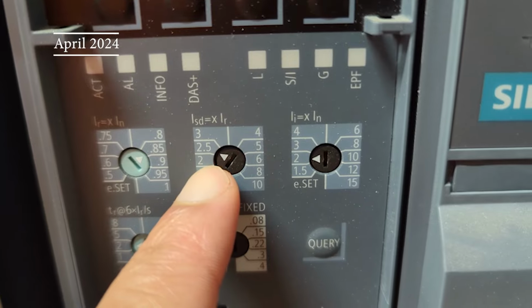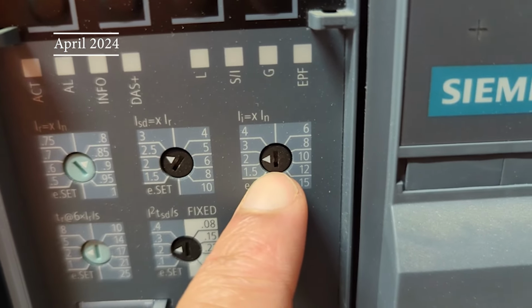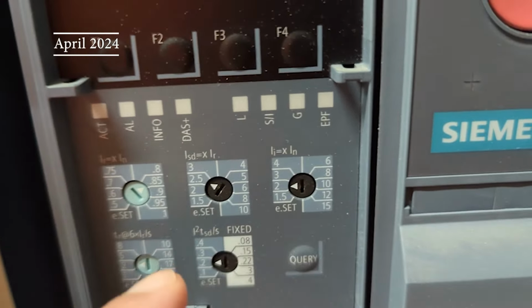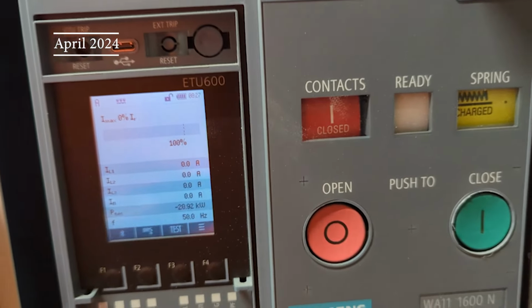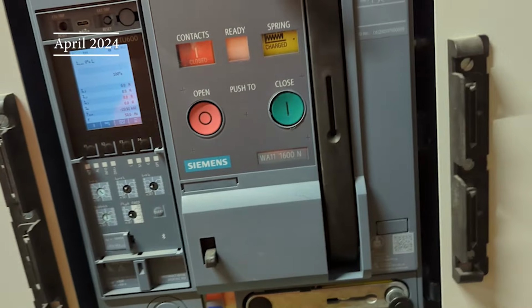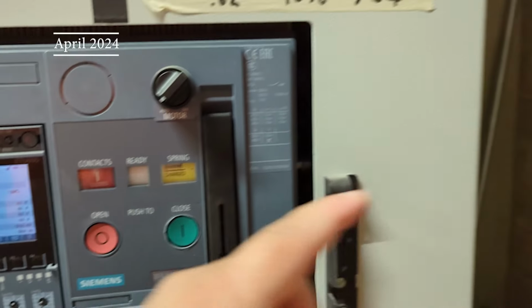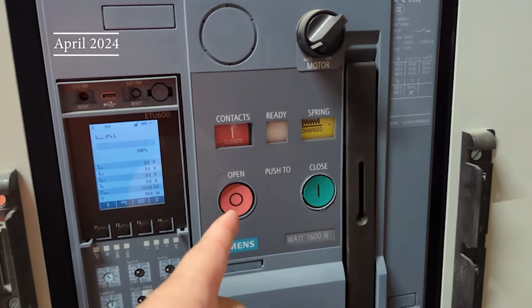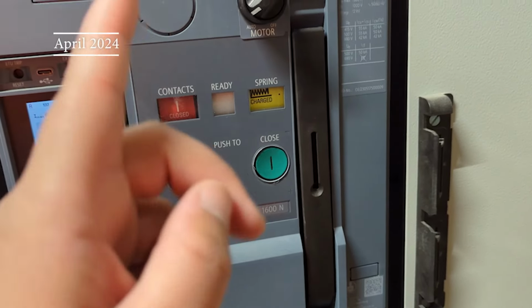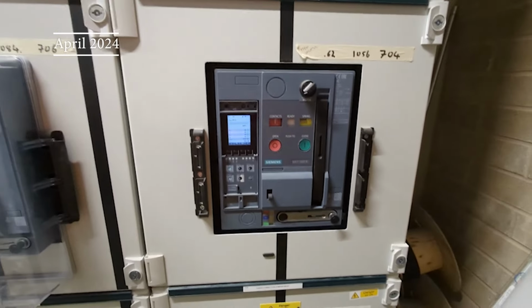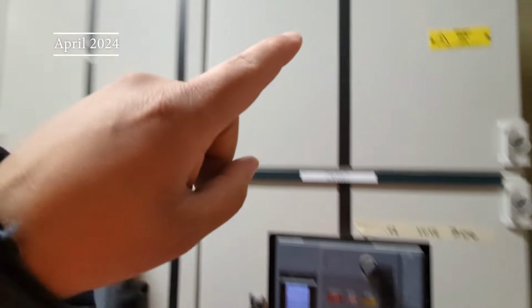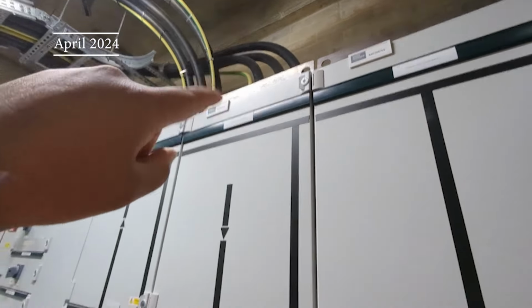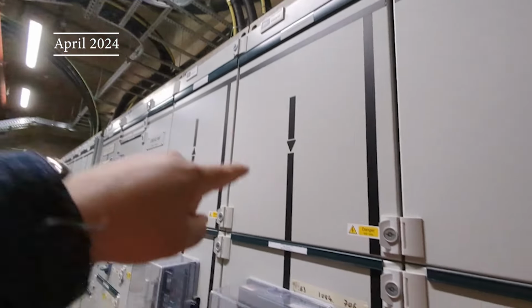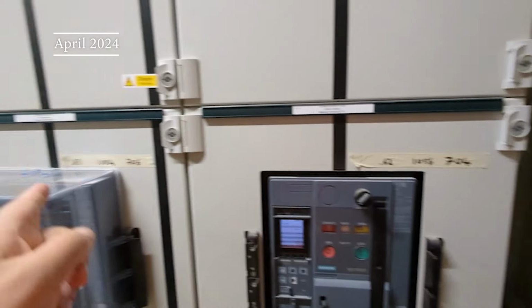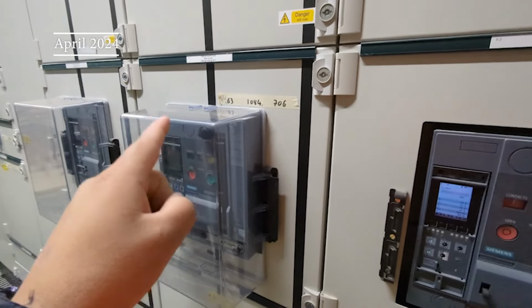Then you've got short time duration, and you've got instantaneous. So these LSI settings are currently, for whatever reason, not correct because it's not blowing when it should be. This is closed at the moment. What should happen is that when this sees 1500 amps, this should open. So this is the main circuit breaker, which isn't blowing at the moment. This feeds into this circuit breaker, which is fed from the generator. Sorry, actually, opposite way. This doesn't feed this. This is fed from the generator, so ignore this ACB.